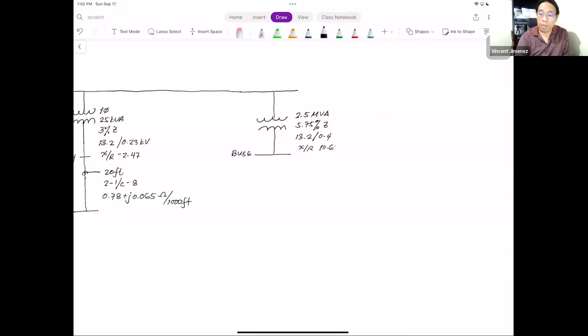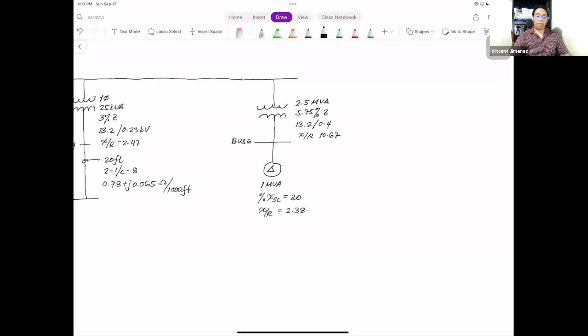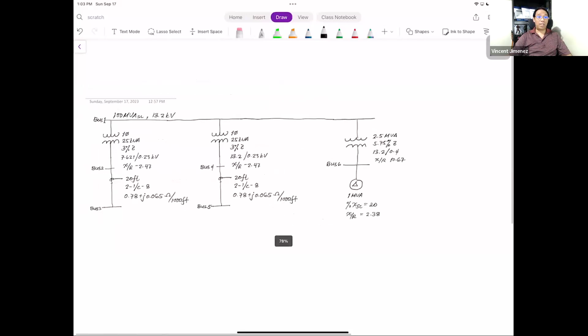Okay, and then connected to this bus, we will get a lump load. Okay, lump loads that are contributing to the fault. Pag nagkaroon ng short circuit upstream, etong loads na yan magbubigay ng short circuit current. These are the rotating machines, motors. Okay, induction type, synchronous type. This will provide short circuit contribution at the fault. Okay, so the rating here is 1 MVA lump load. Okay, percent X short circuit is assumed at 20%. Okay, and an X over R ratio of 2.38. Okay, so yan yung ating network. This is quite a typical setup in a distribution level.